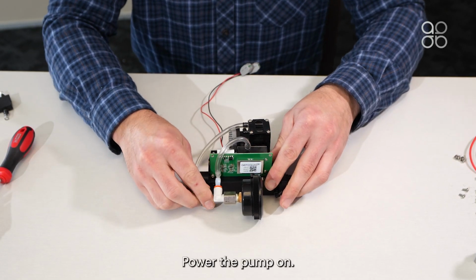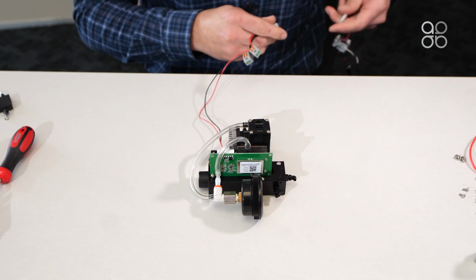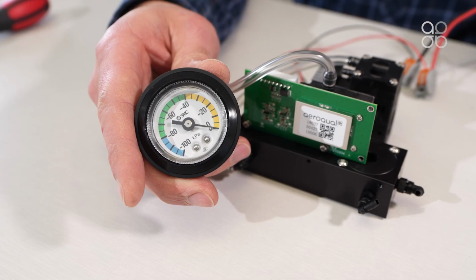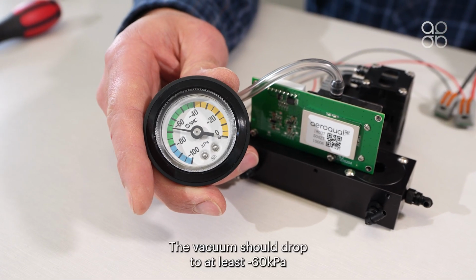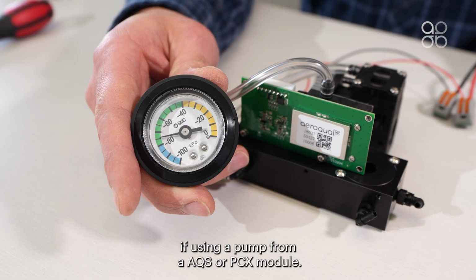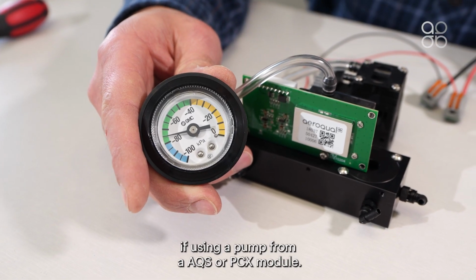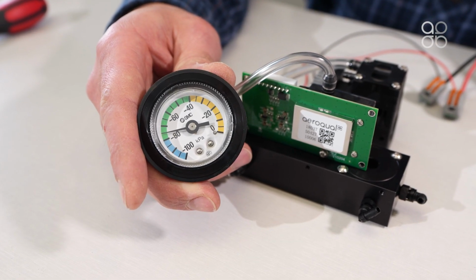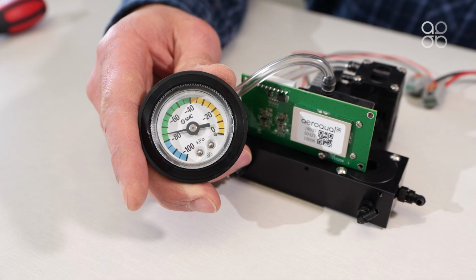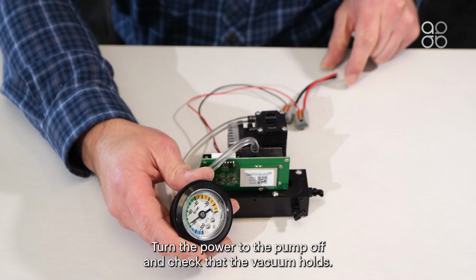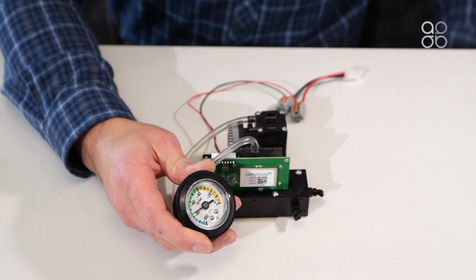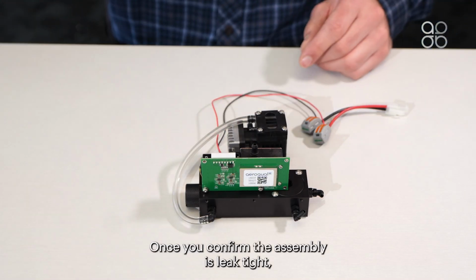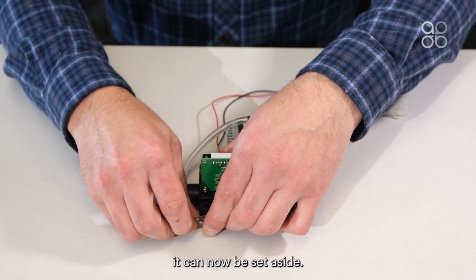Power the pump on. The vacuum should drop to at least -60 kPa if using a pump from an AQS or PCX module. Turn the power to the pump off and check that the vacuum holds. Once you've confirmed the assembly is leak tight, it can now be set aside.